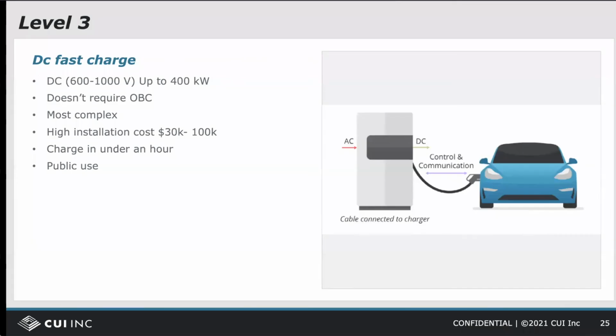Level 3 is for DC charging and sometimes called DC fast charging. These chargers apply a high voltage of up to 1000 volts DC directly to the battery management system. SAE divides DC charging into two levels with 80 and 400 kilowatt limits, while IEC defines mode 4 as fast DC charging but only allows for up to 400 volts and an 80 kilowatt limit. DC fast chargers can reduce the charge time to under an hour and push them much closer to the refueling time of a gas-powered vehicle.